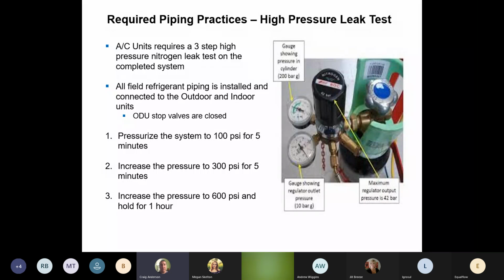Let's increase it up to 500, 600 PSI. Let's get it up there. We can get up to those pressures on a 410A system if that unit is out in the heat and the coil's blocked outside. We can get high pressures on that before that compressor is going to kick off. Compressors usually kick off just over the 500 mark. So let's make sure we do our nitrogen check. And once that compressor turns off, the discharge valve will go. So let's make sure that we're nitrogen checking at a high PSI, so we know that we have no leaks. And let's check it for an hour.